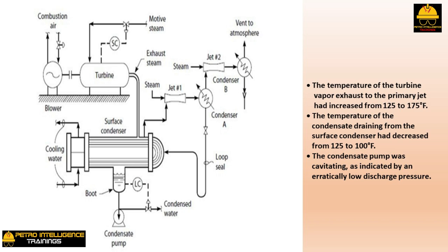The condensate backup sub-cools the condensate but reduces the number of tubes exposed to condensing steam, forcing the steam to condense at a higher temperature. In effect, condensate backup has reduced the surface area available to condense the steam. The higher the condensation temperature, the higher the condensation pressure of the steam — just like a deaerator. It is the vapor outlet temperature of the surface condenser, rather than the condensate outlet temperature, that determines the real condensing temperature and pressure of the exhaust steam.